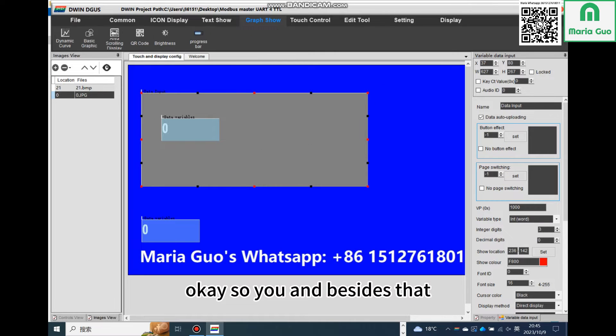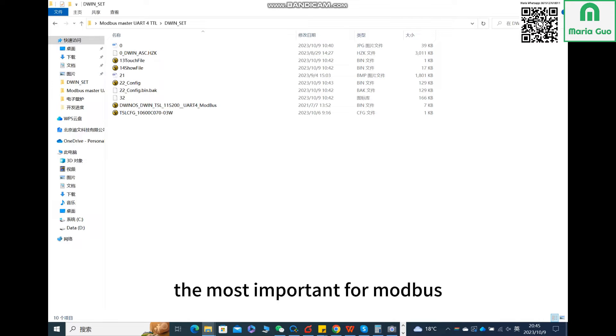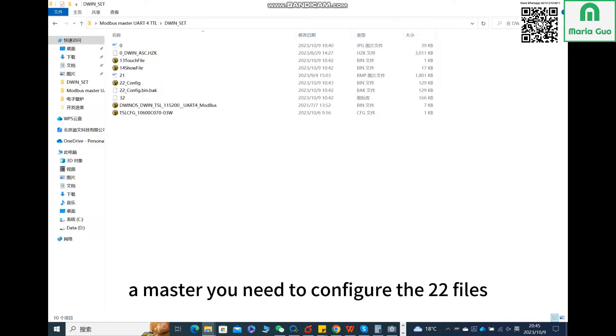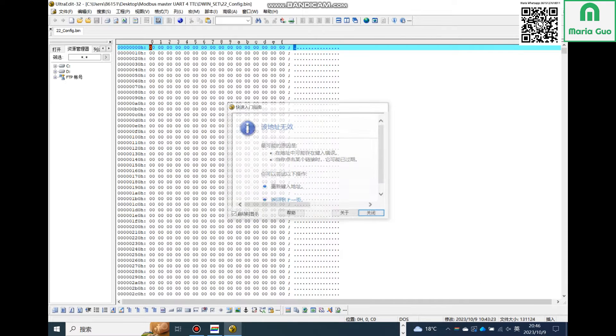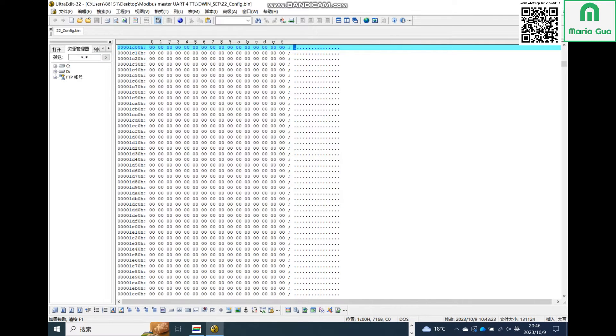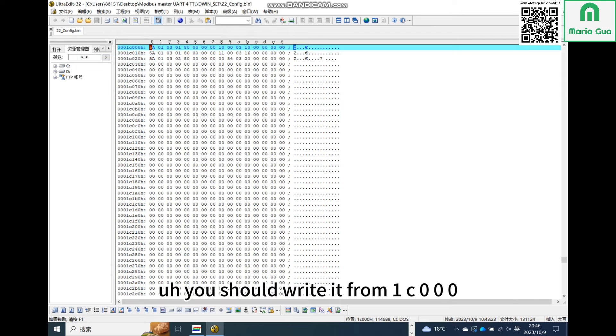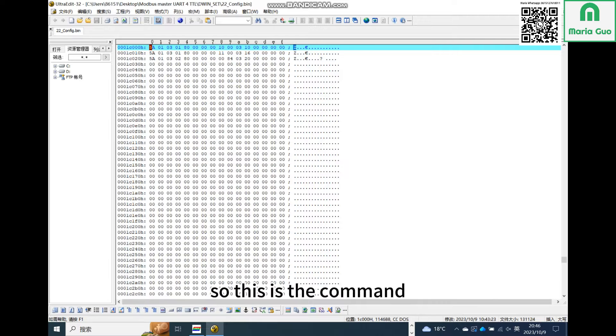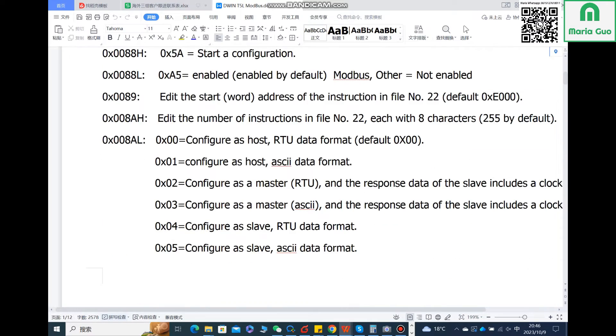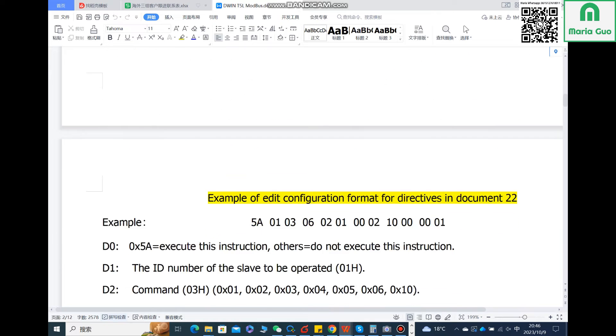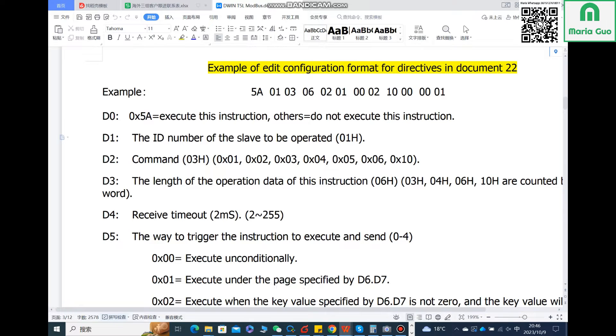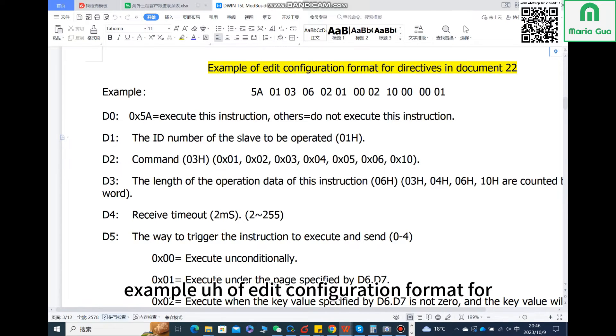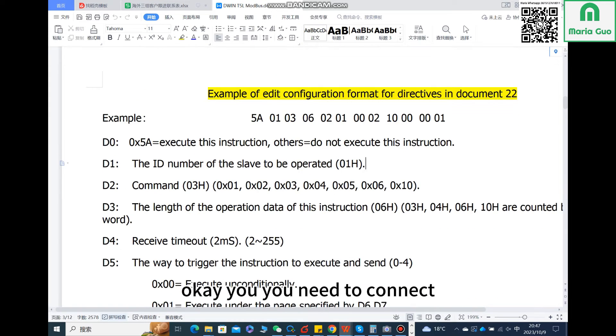Besides that, the most important for Modbus master is you need to config the 22 files. It has a special address. You should write it from 1C000. This is the command you need to know. Here is the example of edit configuration format for directives in document 22. You need to connect the master and slave together. So here first is 5A, which means execute this instruction. Then this is the slave ID, and then this is the command you need to use.